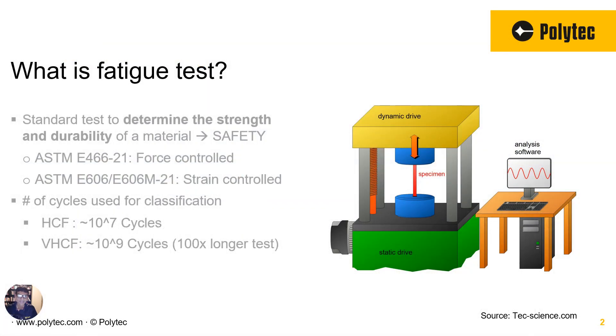In this case we are talking about a strain tester specifically designed for high cycle fatigue testing or very high cycle fatigue testing. But let's start with the definition of fatigue test. In a fatigue test the material under test goes through a cyclic loading where we fix the frequency and then depending on which ASTM standard you're following you may be controlling to keep the force constant or you may be controlling to keep the strain constant.